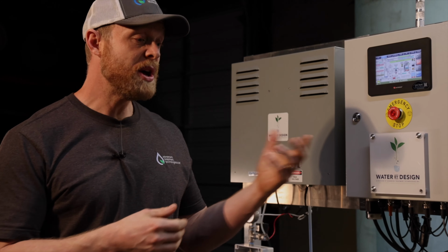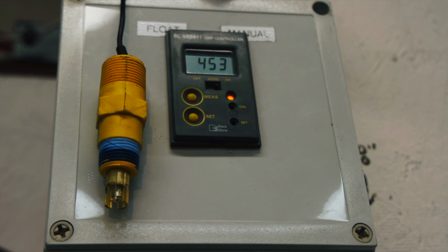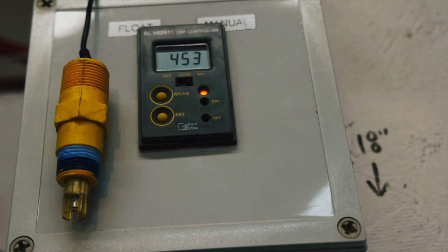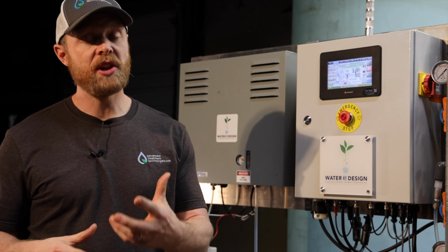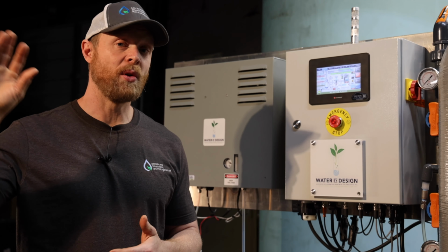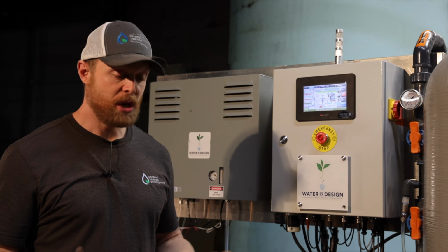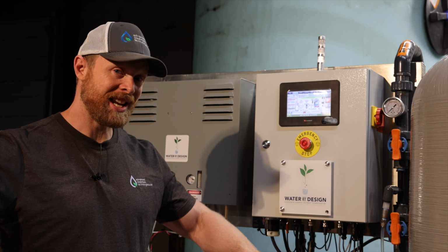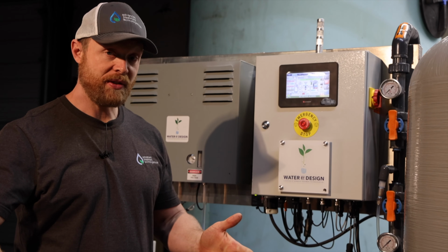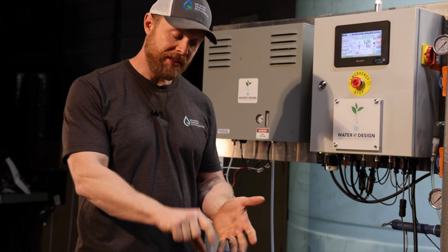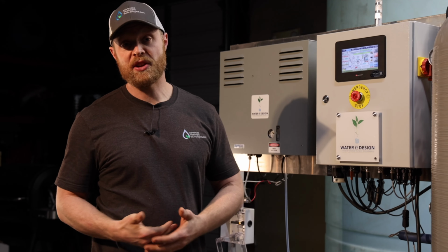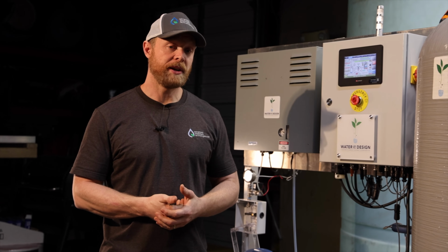And so we build a panel that you can see there, this little yellow ORP probe, and it's designed to be mobile. So what we recommend is that you build a manifold. If you don't want to do this in every grow room, do it at least in the one that's furthest away from the system. Usually put a ball valve in and a ball valve out so that we can isolate and not make a mess. Then you have a union and a union so you can take it out at any time if you ever should need to. And then in the middle, there'll be a T with 1/2-inch thread. That ORP is a 1/2-inch thread probe.